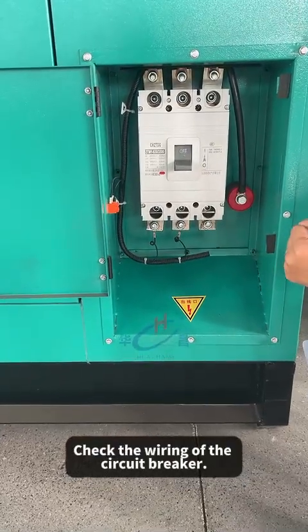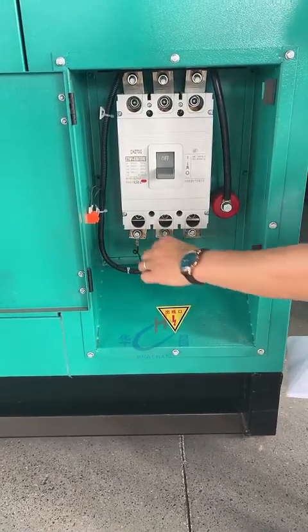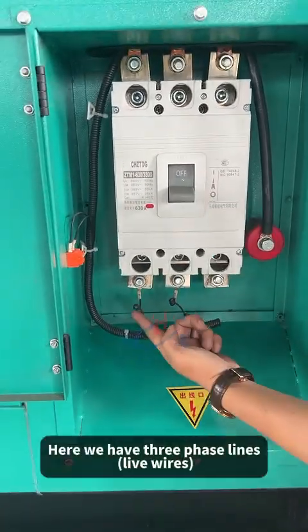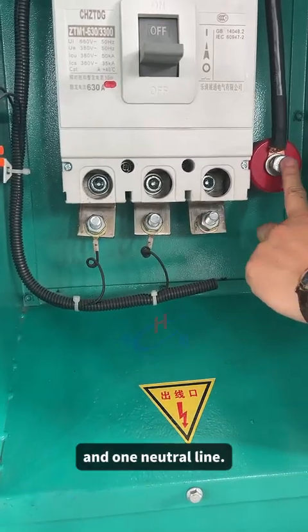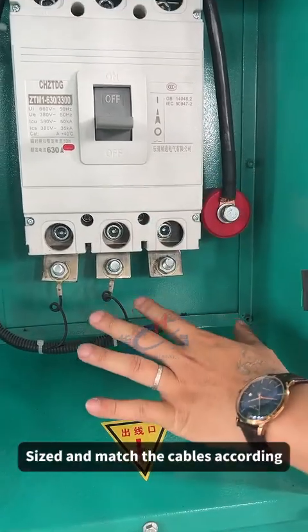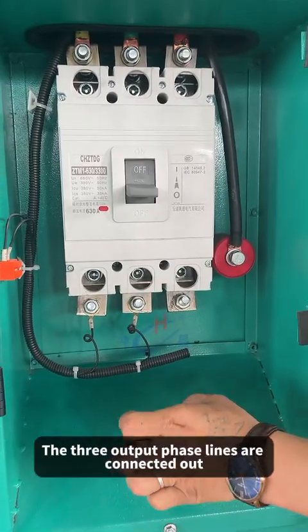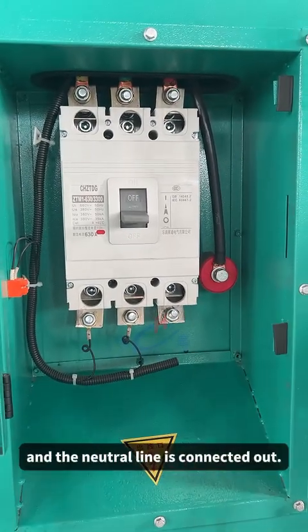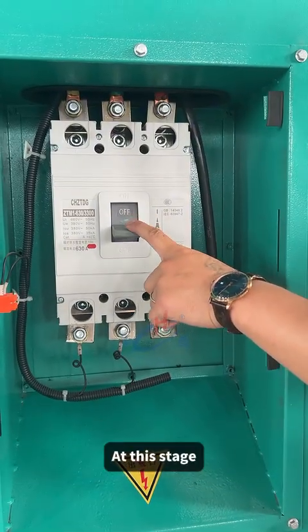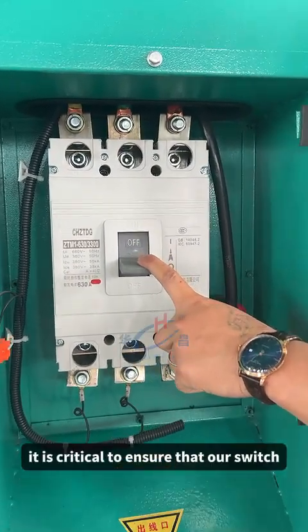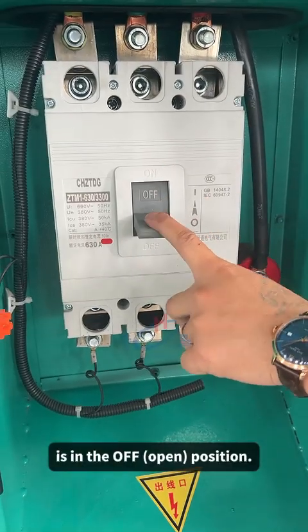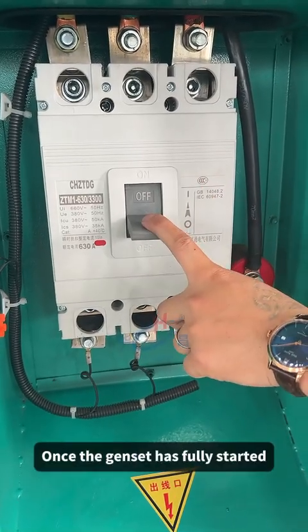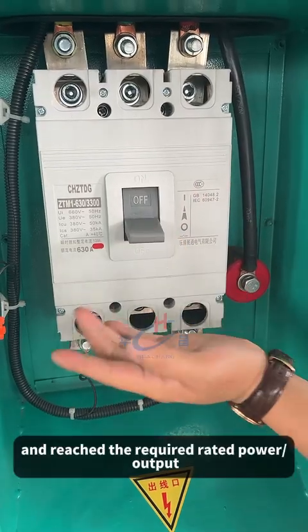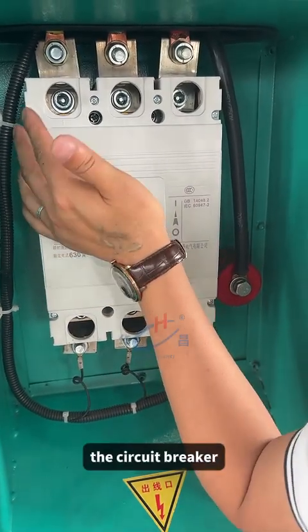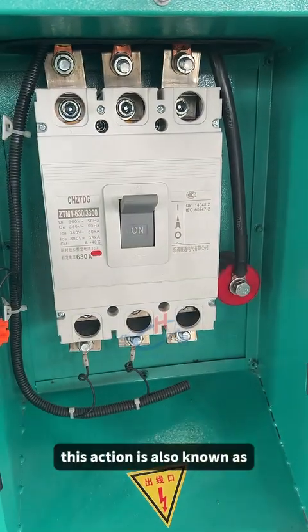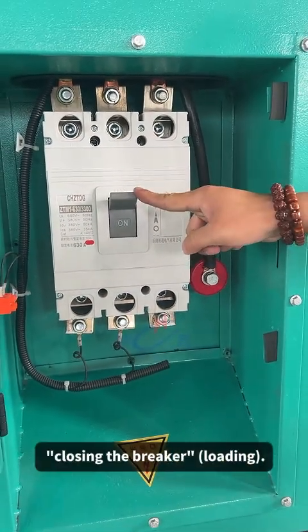Step 4. Check the wiring of the circuit breaker. Here we have 3 phase lines (live wires) and 1 neutral line. Size and match the cables according to the capacity of the genset. The 3 output phase lines are connected out and the neutral line is connected out. At this stage, it is critical to ensure that our switch is in the off (open) position. Once the genset has fully started and reached the required rated power output, you can switch on (close) the circuit breaker. This action is also known as closing the breaker, loading.